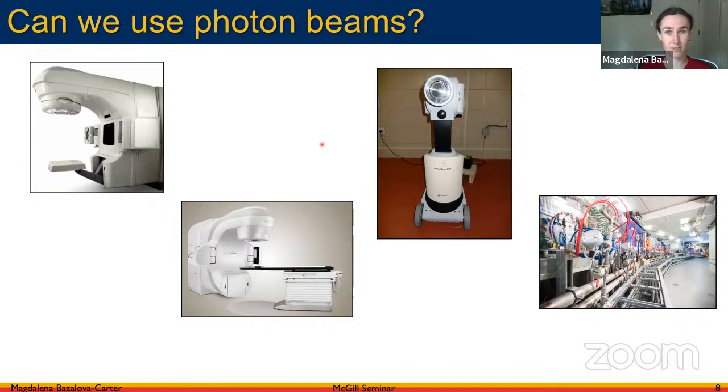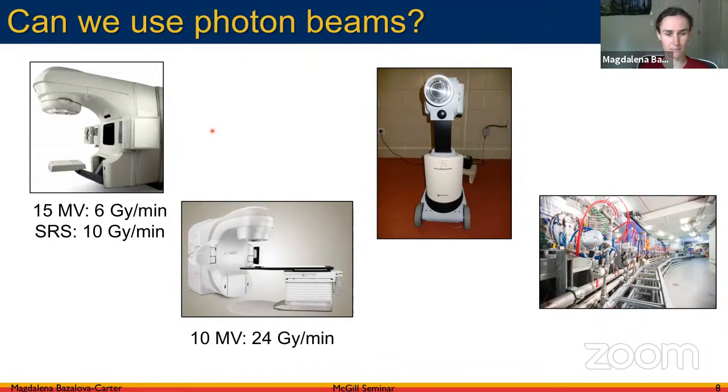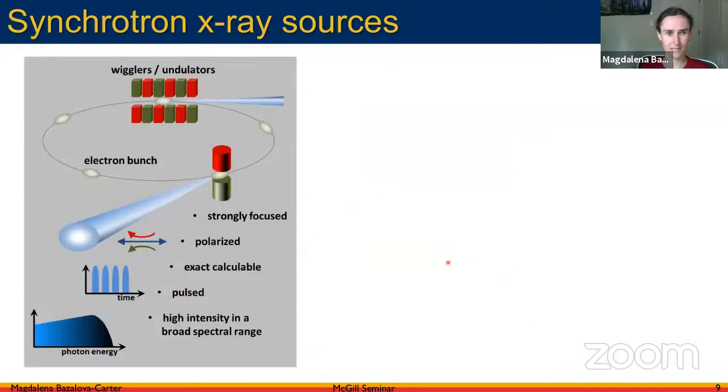What photon sources can we use? Typical linacs deliver 10 Gy/min in SRS mode, or 6 Gy/min — these are per minute, not per second, far from the 40 Gy/s target. Flattening-filter-free TrueBeam delivers about 24 Gy/min. HDR machines deliver about 1 Gy/min. However, synchrotron sources can deliver about 10 kGy/s and have been used for flash radiation therapy.